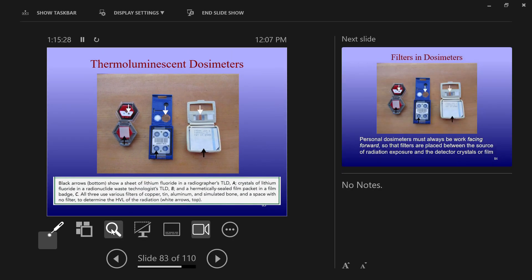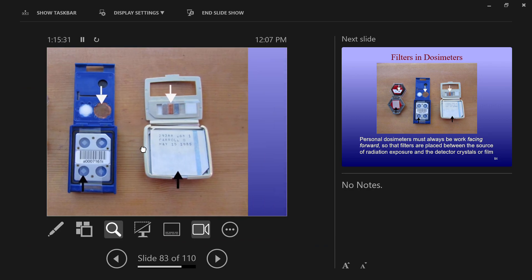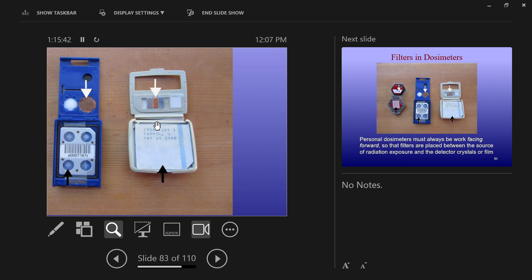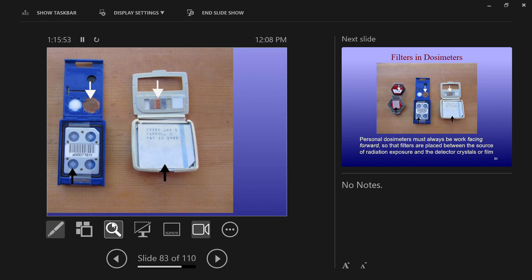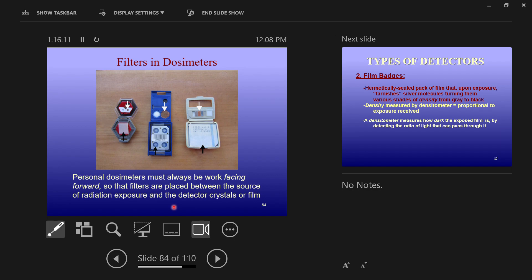You can see those different little copper pieces. So you can see they put little tiny squares of material, and then from those spots on the badge that hide behind those materials, if the radiation is getting through the material, you can infer how much radiation dose to some certain part of the body. These badges must always be worn facing forward so that the filters are placed in front of the part of the badge that detects the radiation, so they're between the source of radiation and the detector. That's why we always have them wearing with our name facing out.